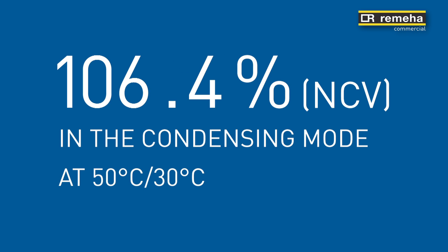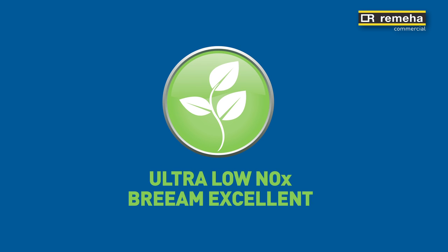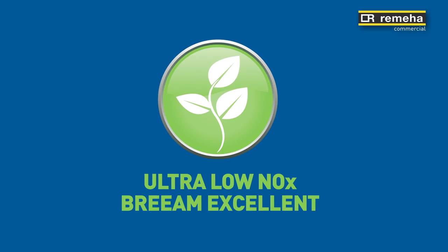The Remeha GAS 310/610 ECO PRO range delivers exceptionally high efficiencies of 106.4% net calorific value in the condensing mode, with a flow of 50 degrees centigrade and a return temperature of 30 degrees centigrade. Together with excellent ultra low NOx emissions of less than 36 mg per kilowatt hour at 0% O2, and minimum CO2 emissions.